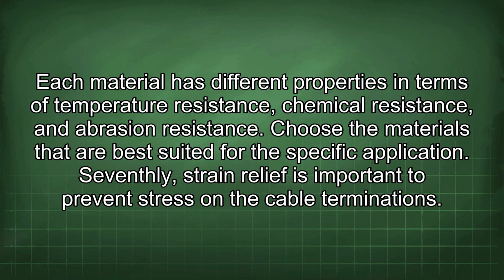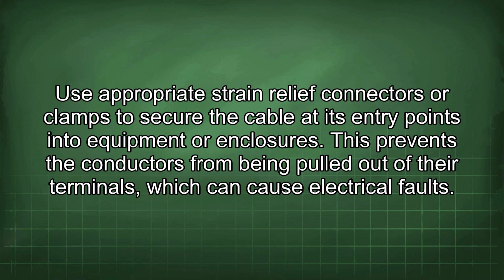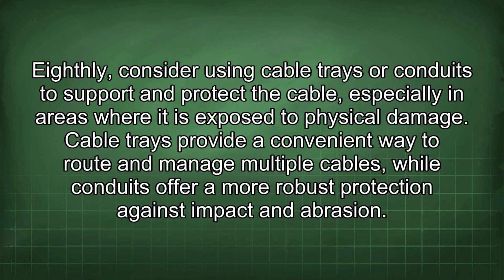Seventhly, strain relief is important to prevent stress on the cable terminations. Use appropriate strain relief connectors or clamps to secure the cable at its entry points into equipment or enclosures. This prevents the conductors from being pulled out of their terminals, which can cause electrical faults. Eighthly, consider using cable trays or conduits to support and protect the cable, especially in areas where it is exposed to physical damage. Cable trays provide a convenient way to route and manage multiple cables, while conduits offer a more robust protection against impact and abrasion.